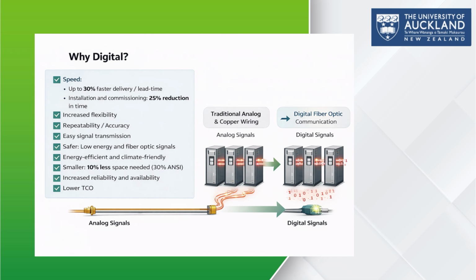So the first question would be, why digital? As we move towards digital substations and digital technologies, the advantages become very clear. Digital solutions offer up to 30% faster delivery and lead time, and installation plus commissioning time can also be reduced by about 25%. This means projects can go live quicker and with fewer delays. And the digital architectures are modular and scalable, so expanding or modifying the system becomes much easier without major redesign. We also gain higher accuracy, ensuring consistent performance across the entire system.